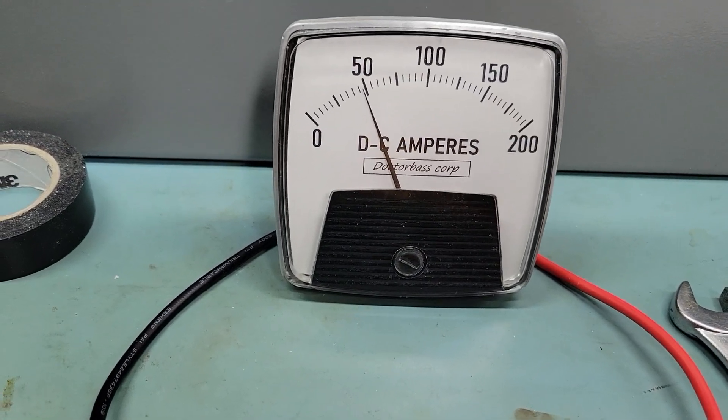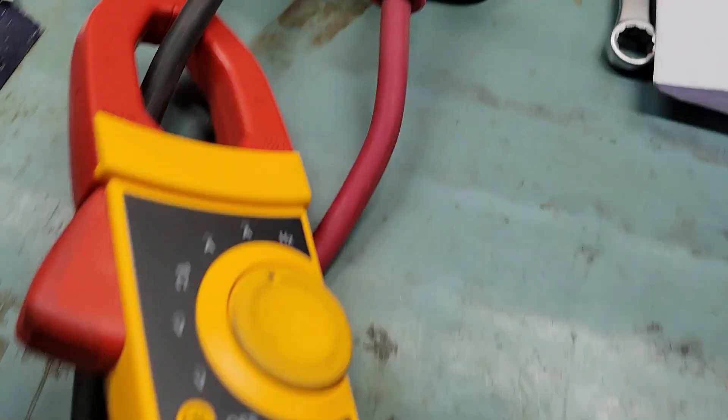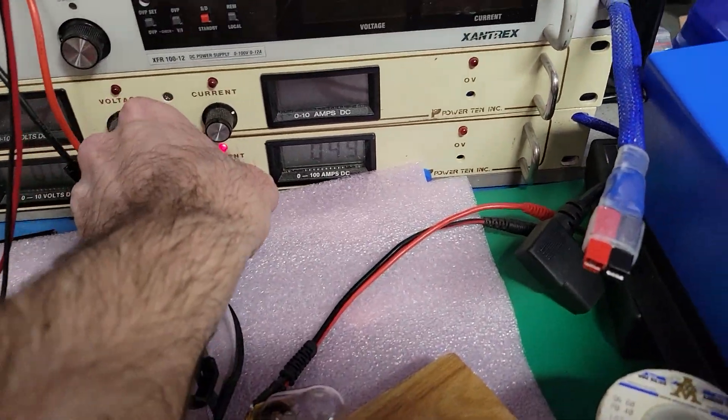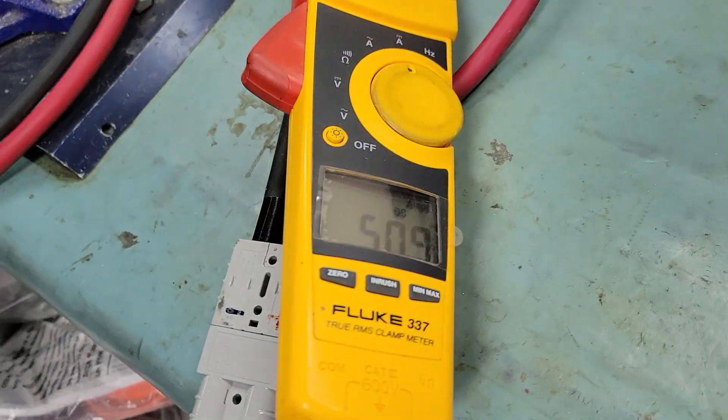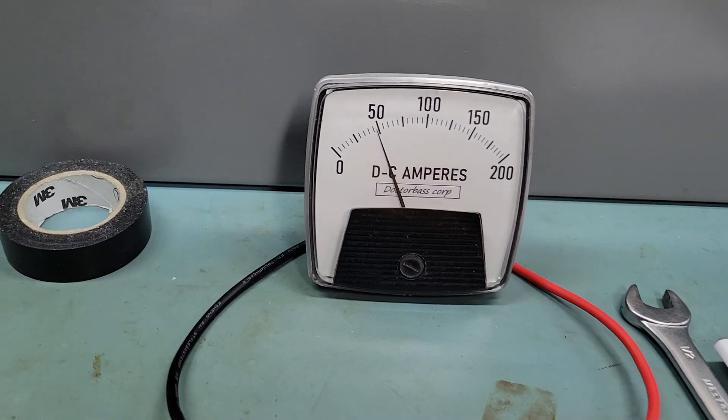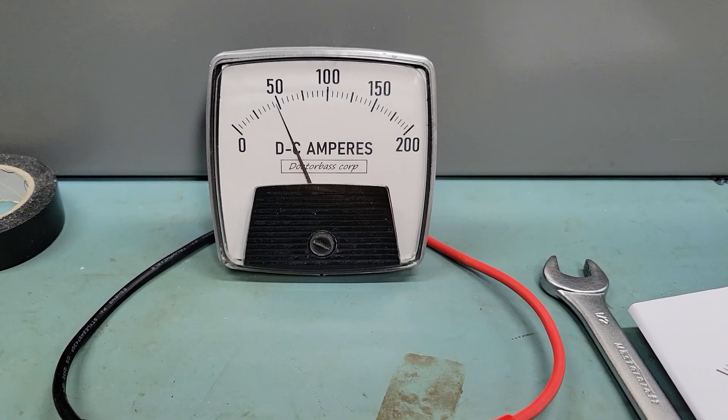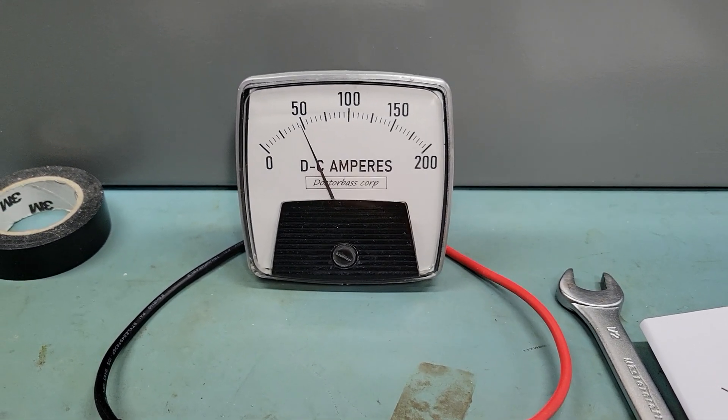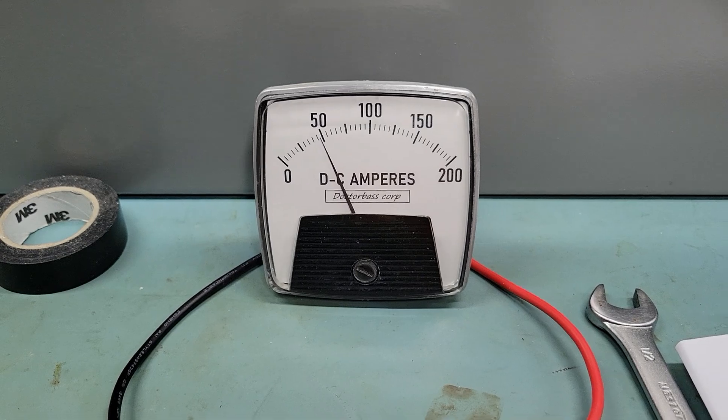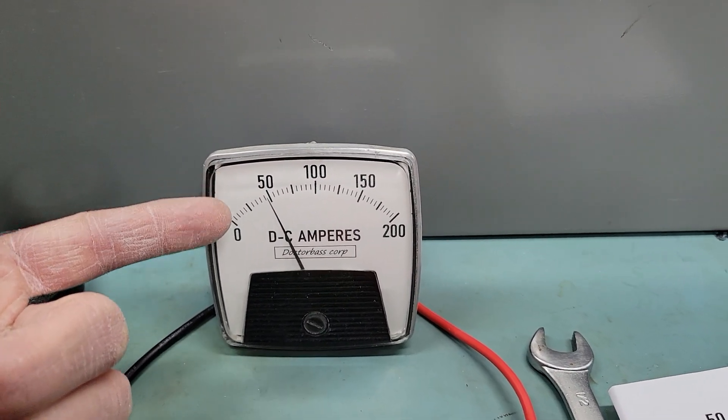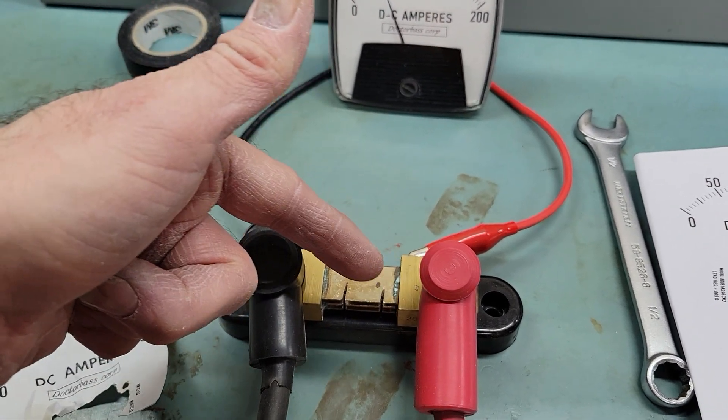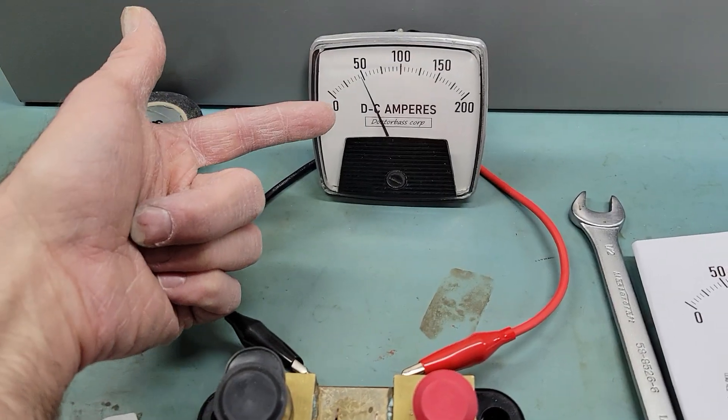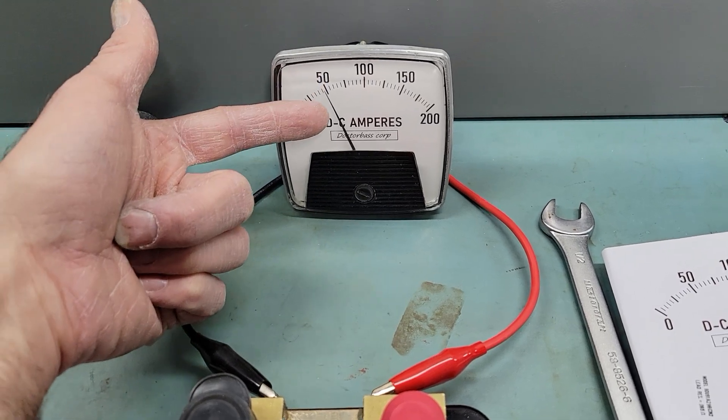So about 50. The meter is not exactly 50. I will just increase a little bit. Maybe it's a trade-off between the Fluke and this one, but you see we're very close. If it's not giving exactly the reading you want, let's say that there's some missing amps here, it means that there's not enough voltage drop across this resistance in order to create what is required to have the needle at the 50 indication.